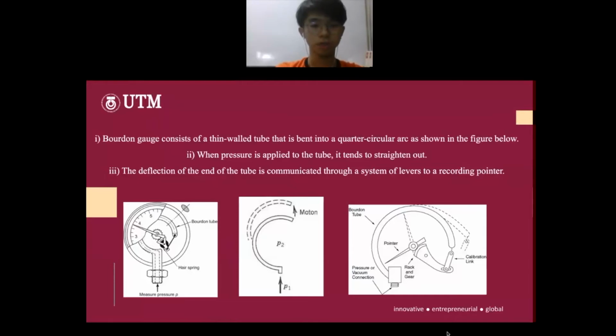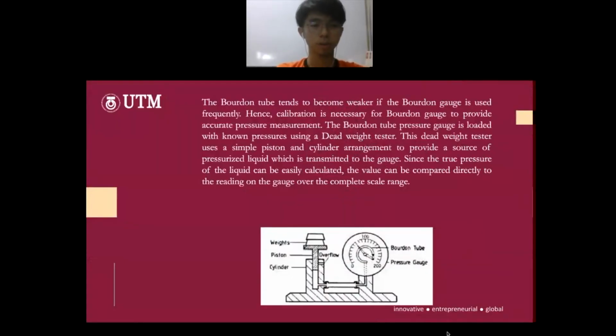For the third image, you can see the deflection of the tube. The deflection of the end of the tube is communicated through a system of levers to a recording pointer. So when the tube expands out, it moves the calibration link, and the rack and gear will start to rotate. The rack and gear will rotate the pointer too and show us the reading. The Bourdon tube tends to become weaker if the Bourdon gauge is used frequently. Hence, calibration is necessary for the Bourdon gauge to provide accurate pressure measurement.